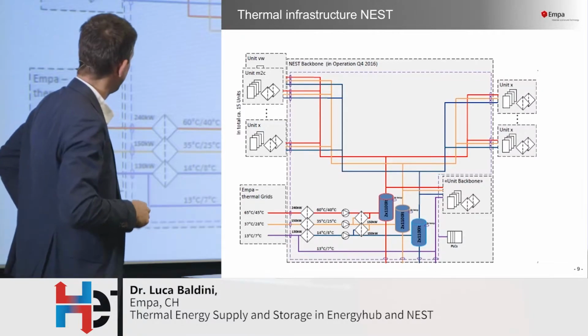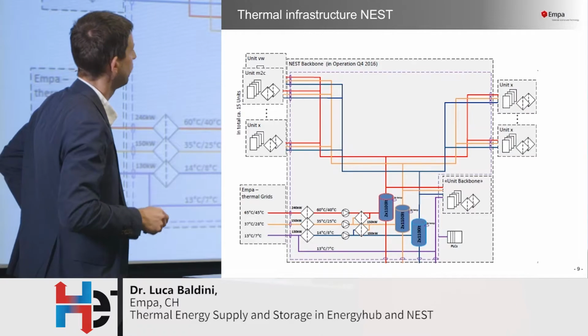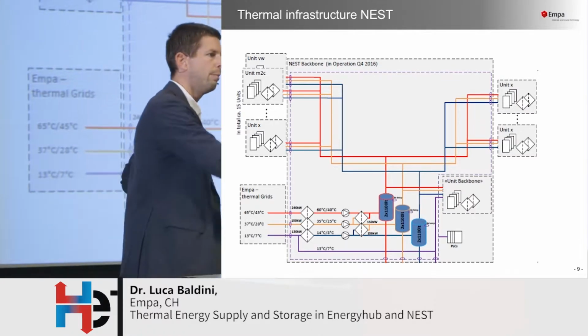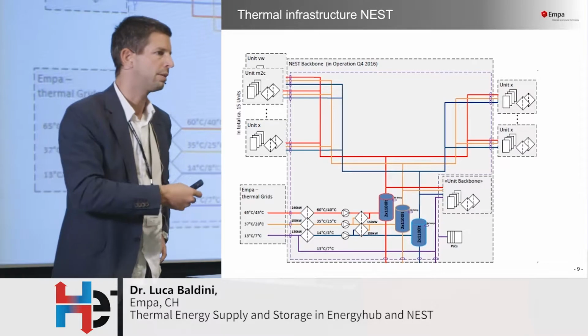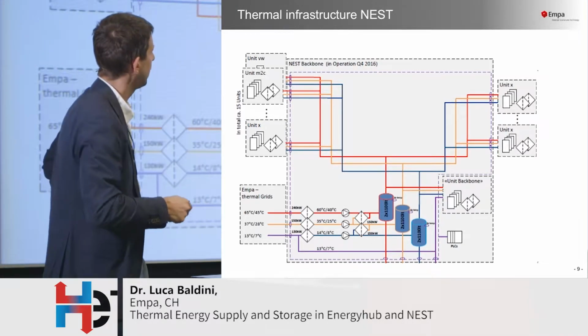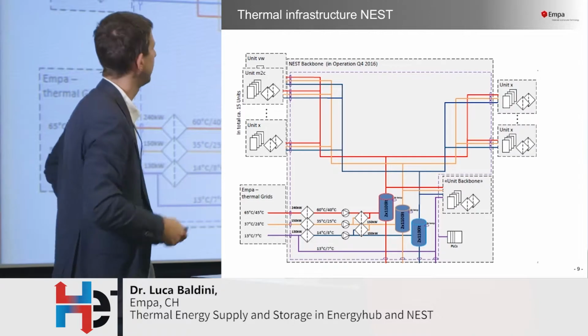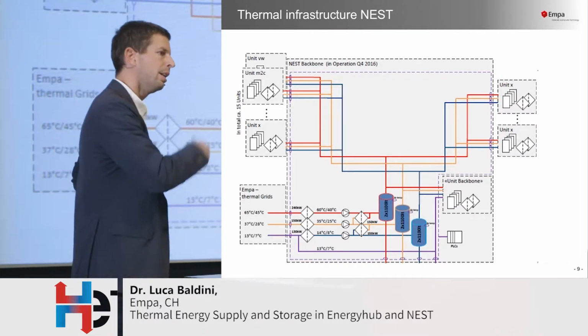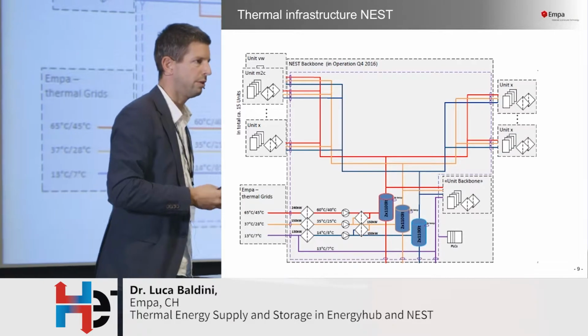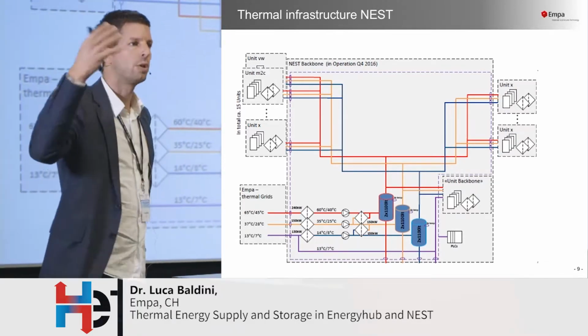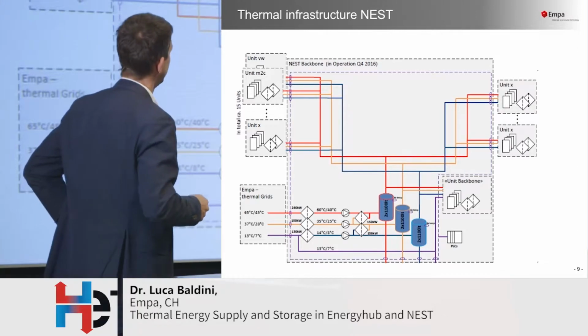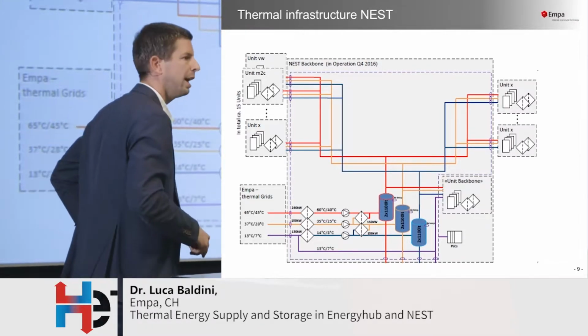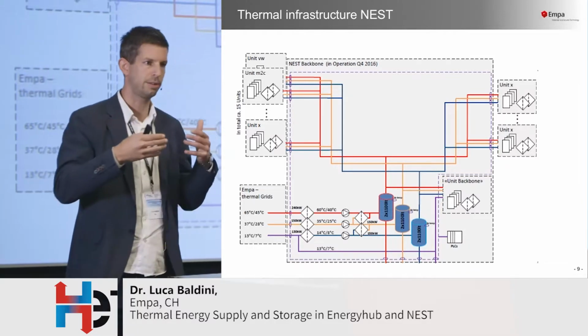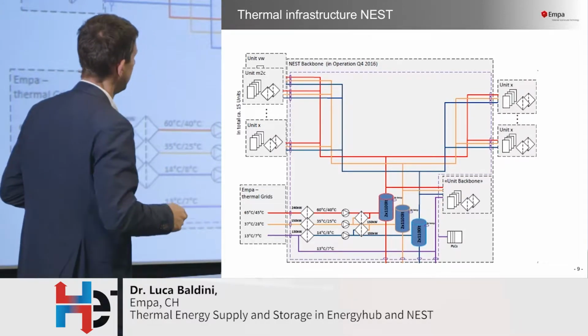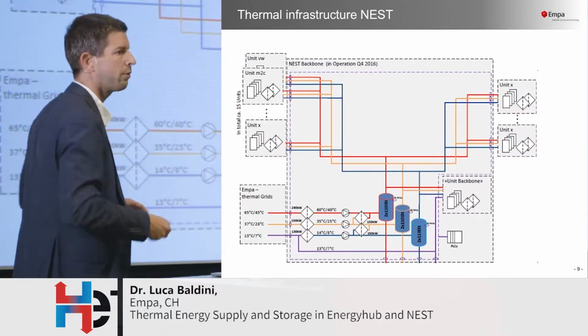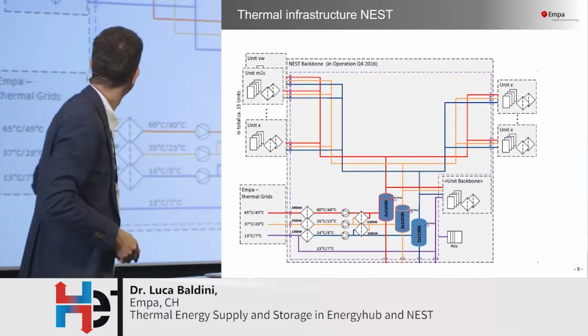We use those grids to withdraw energy, but we can also dump energy into those grids on different levels. A unit, being a building, can say, I want to have my local heat pump, and use the low temperature grid as if it was a ground heat exchanger for my heat pump. I can have my solar collectors and dump heat at the high temperature and introduce it in this level. Since Nest is not a building but a vertical district, it's also a district system which allows for redistribution of energy streams between different units.